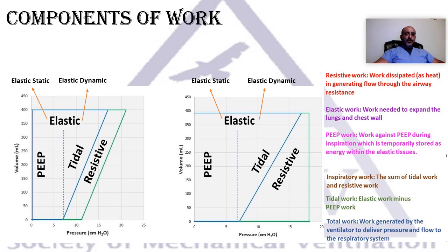There's a newer concept called the inspiratory work, in which they ignore the PEEP and remove the PEEP work from the equation, because it's only a static component. Basically, it will be the sum of the tidal work and the resistive work.